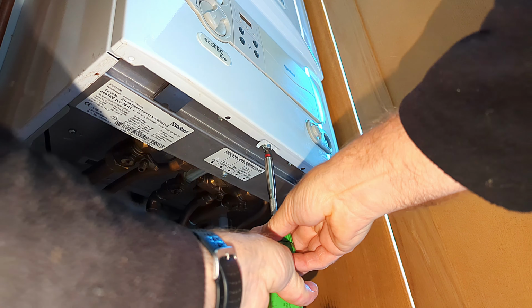Now I'm just isolating the boiler from the rest of the central heating system. To do that I use a 4mm Allen key bit. I just put it into the Allen key slot and then turn it a quarter of a turn to close the flow valve, and then I do the same on the return valve. So both valves are now isolated, so the central heating system is isolated from the boiler. And I do this because I don't want to drain the rest of the system. The valves are shut when the screwdriver slot goes across the valve, and they're open when they're in line with the valve.